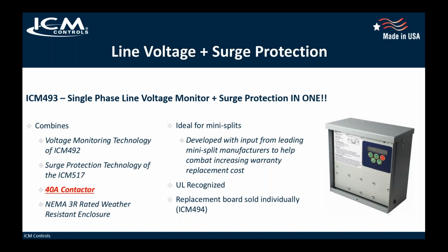You have a 40 amp rated contactor in there that breaks you from the line. Now the difference between this one and the 492 that you saw, as well as the 517, particularly the 517, is that this one's in series with the line. This is going to break you from the main line, whereas the other devices didn't necessarily break you from the main line. Especially the 517 was in parallel, so it definitely did not break you from the main line. And neither did the 492, because it was mostly cutting off low voltage circuits. Whereas this one will, up to 40 amps, break you from that line. It is also a NEMA 3R rated outdoor enclosure, and it is ideal for the mini split market.